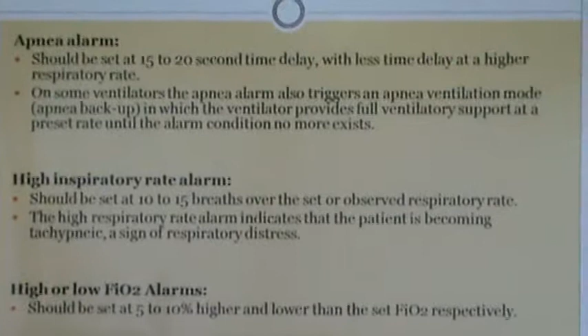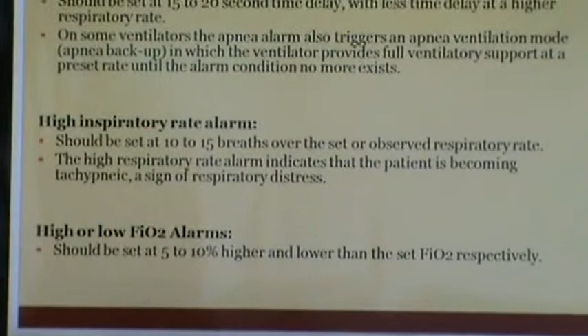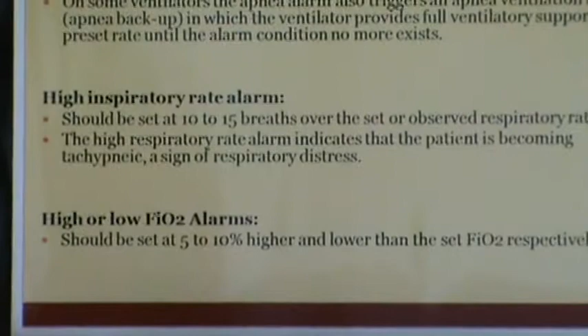Apnea alarm. This is mostly used in NICUs. We just generally set up a 15 to 20 second time delay. And somewhere there is a backup ventilation, if the facility is there. The ventilator immediately shifts to backup ventilation, and you will get that alarm.